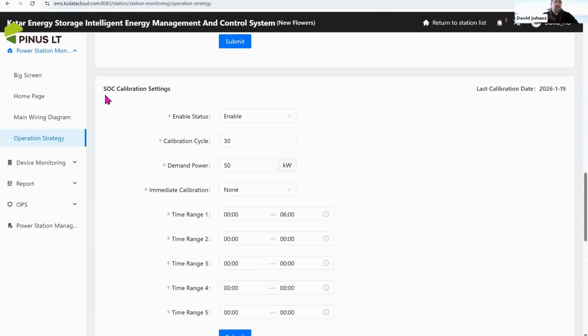And many of the things we can set. For example, the SOC calibration, which is needed to sometimes calibrate the cell voltages of the battery cabinets. It depends on the usage of the battery cabinets. It's only necessary to set if it's not reaching the 100% state of charge regularly.